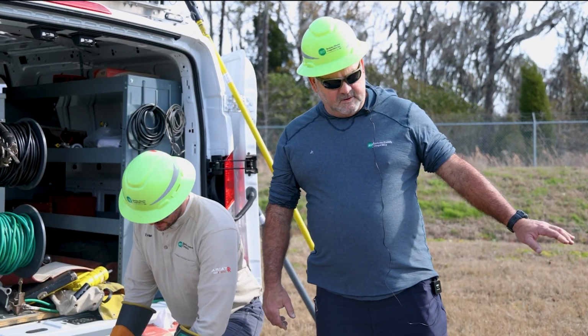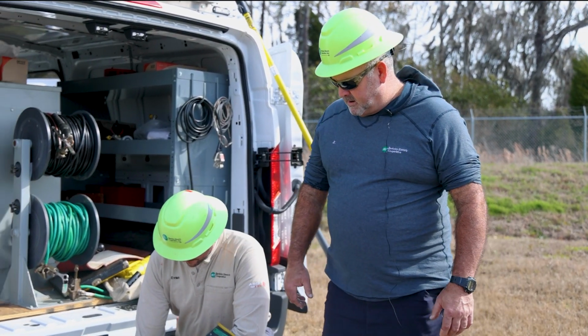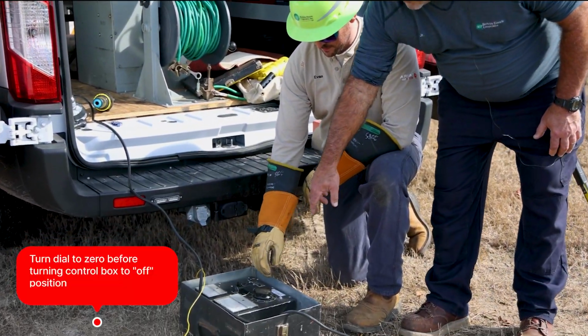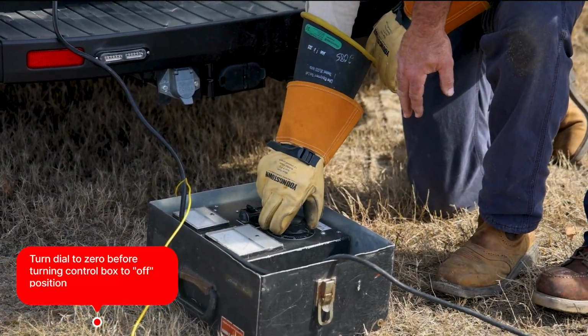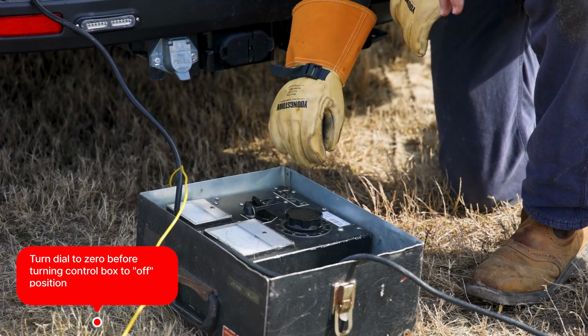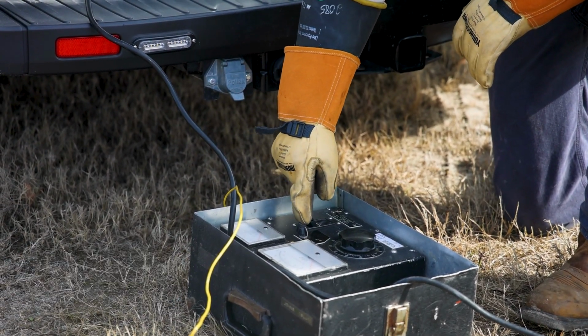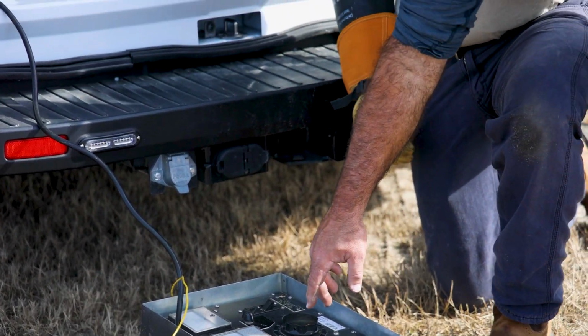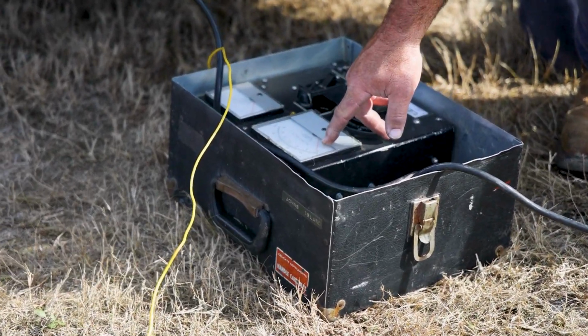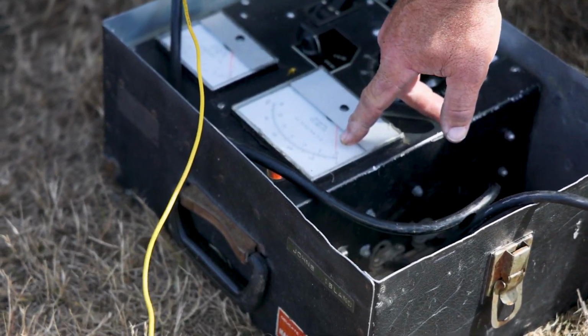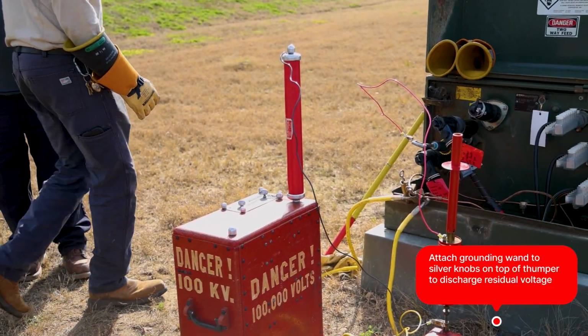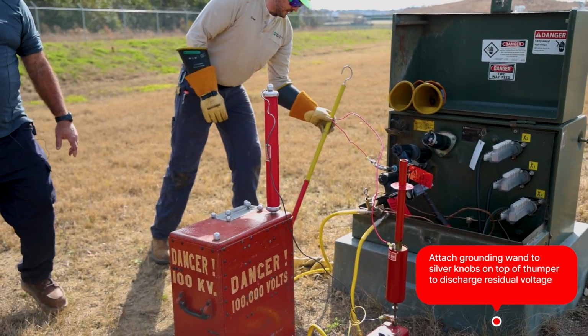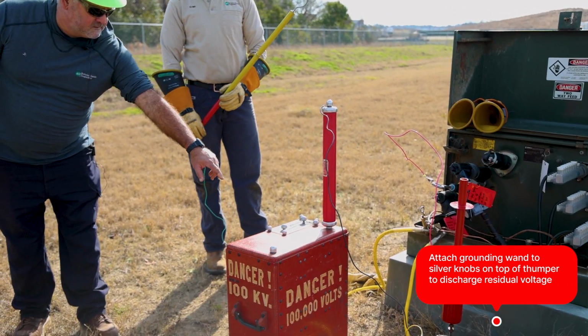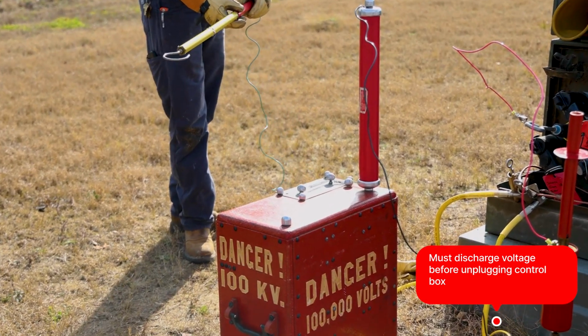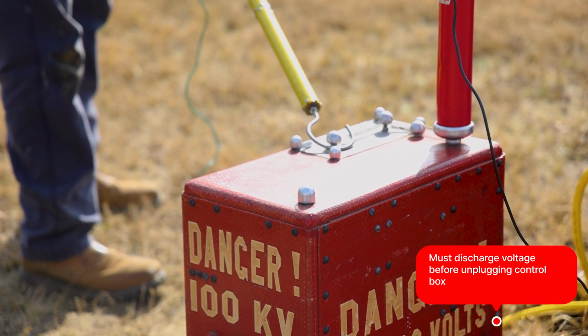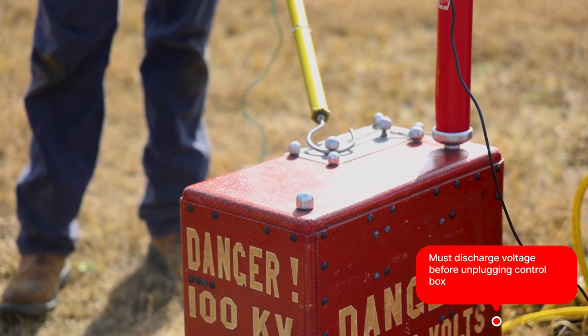Now that we've located our bad primary, you need to turn the dial all the way to 0, and then you can turn the machine off. And if you notice on your dial indicator here, it's holding a little bit of voltage, not much. So then you would want to come over and grab your grounding wand and attach it to the top of the thumper in this area, silver area on top.